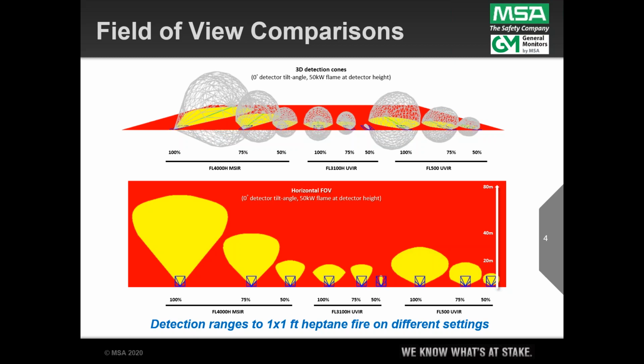The horizontal area of coverage on the FL3100 was roughly 90 degrees, maximum left to maximum right. On the FL500, we're talking 130 degrees, so 65 degrees off center, left and right, a much broader field of view. And then again, the upper panel is the same data, but shown in a three-dimensional perspective.